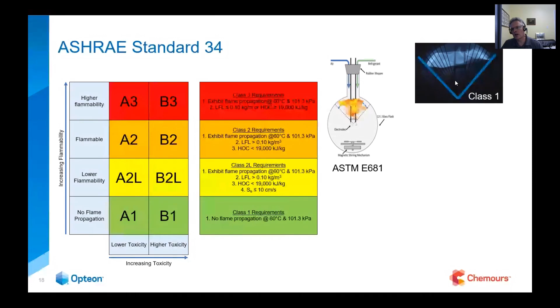But I like to show this test. This is one of the tests that they use to determine flammability. It's called the ASTM E681. So this is what a class 1, what 410A or R22 would look like. And there's combustion, and oddly enough, yes, even with the non-flammables, there is combustion, but the way they determine whether it's combustible or not is, does the flame spread go beyond 90 degrees? So there's a class 1.